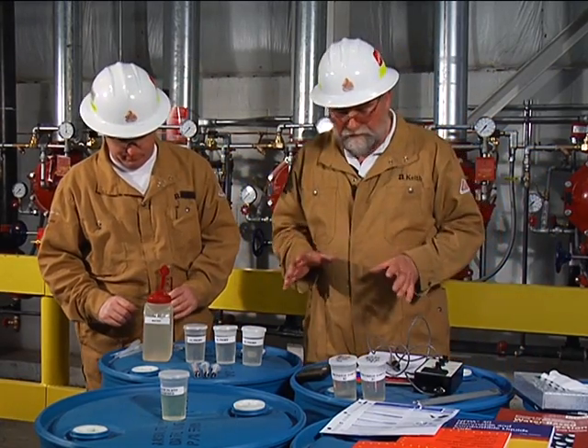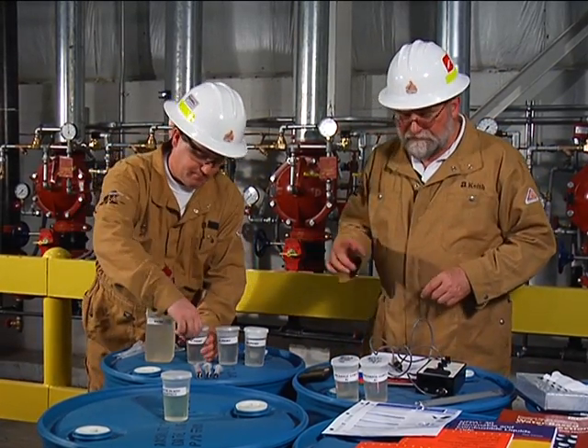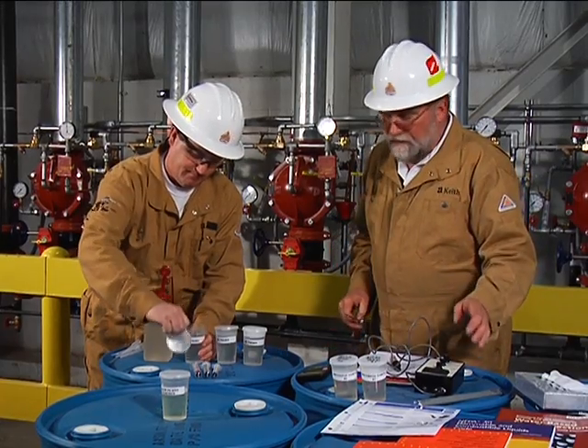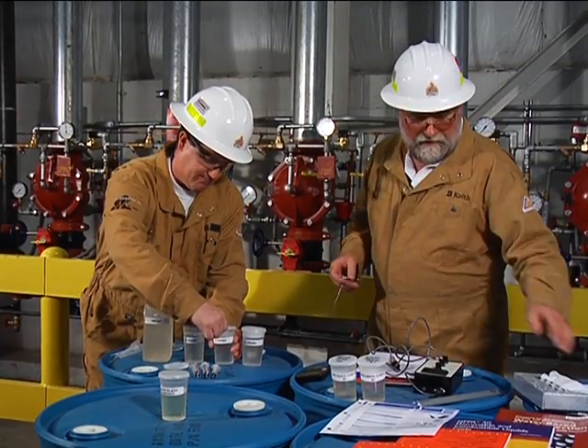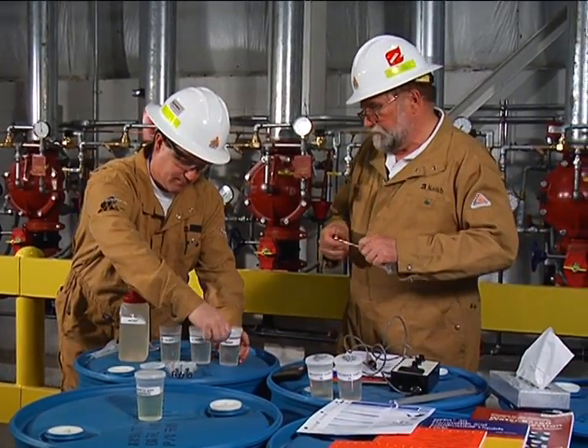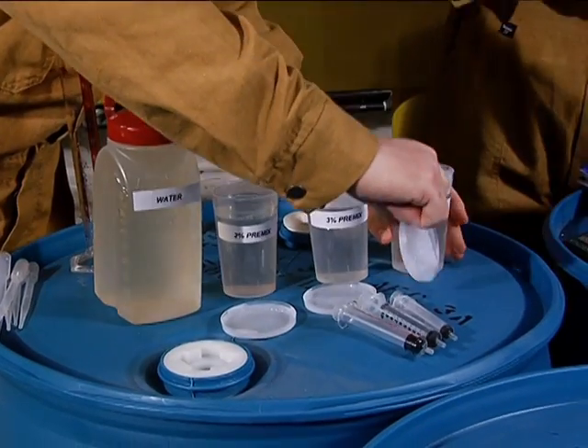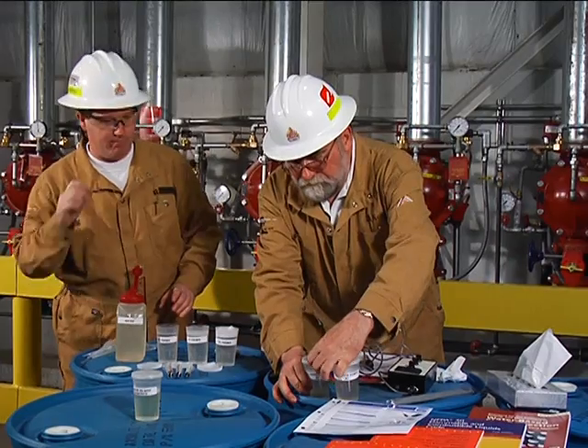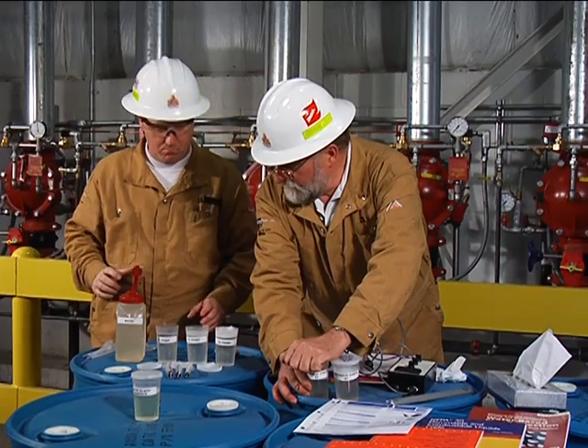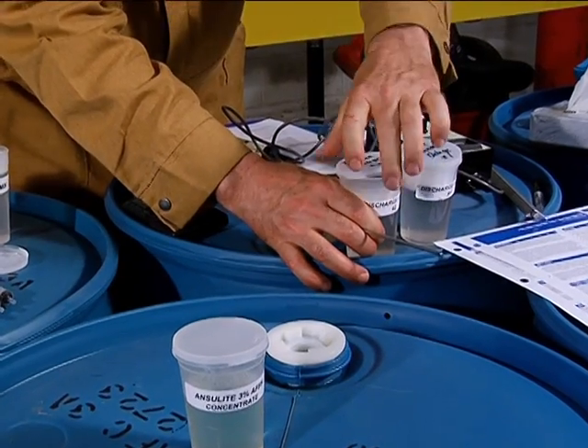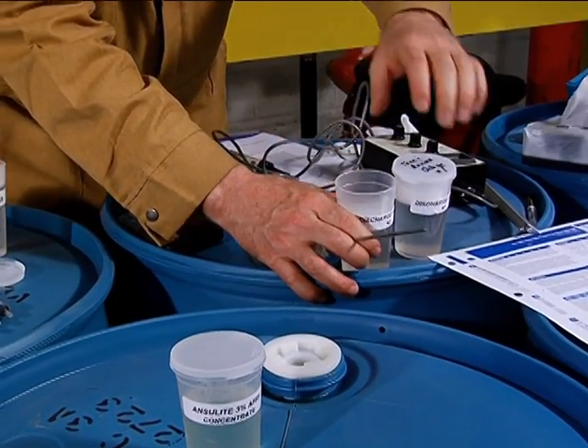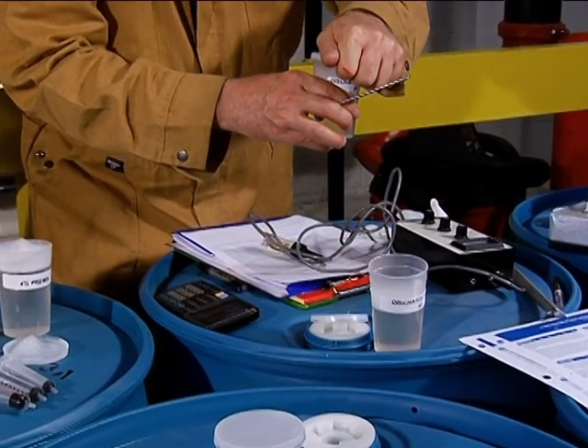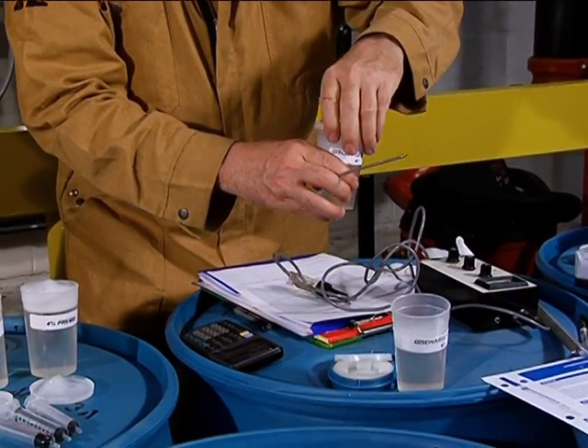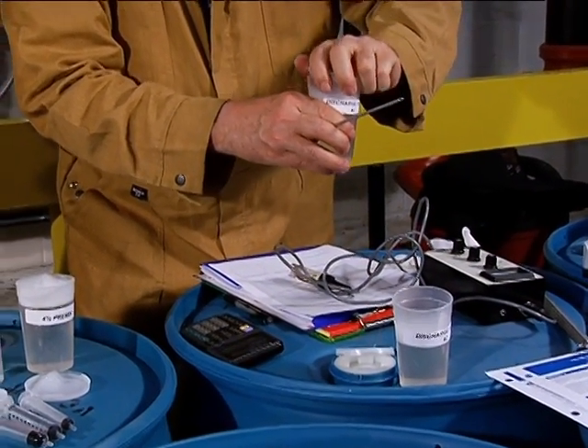First thing we want to do is to check the solution temperatures. When you're doing conductivity measurements, they are temperature sensitive. So we're going to check the temperature of our calibration standards and also of our discharge samples. Make sure that they're within plus or minus 1 or 2 degrees of one another.